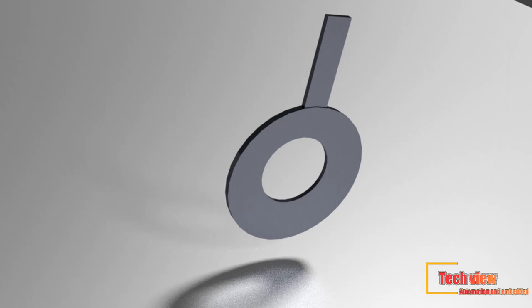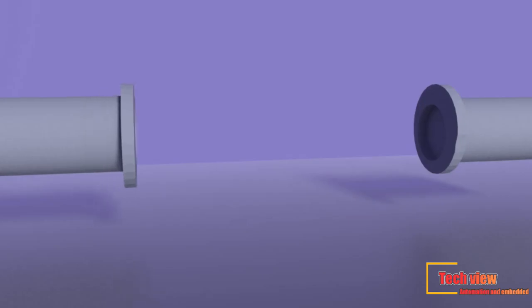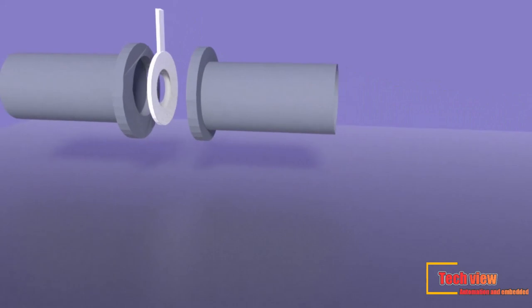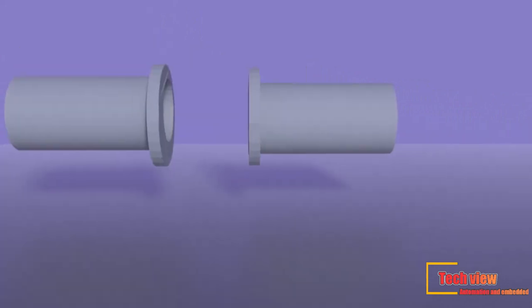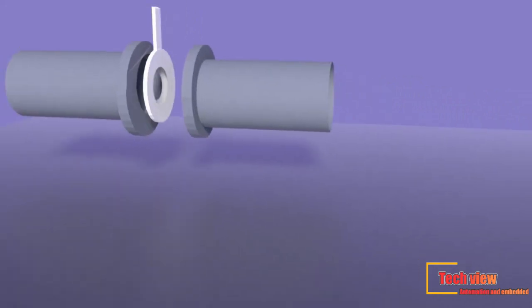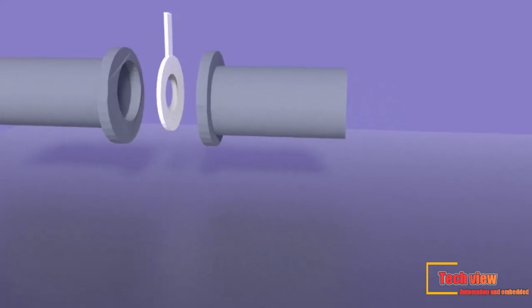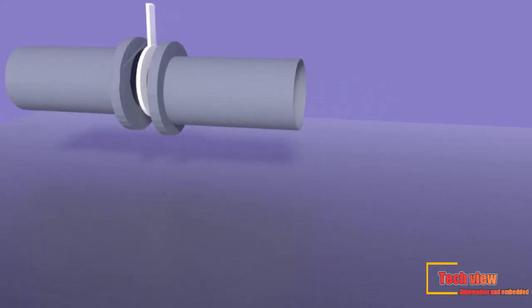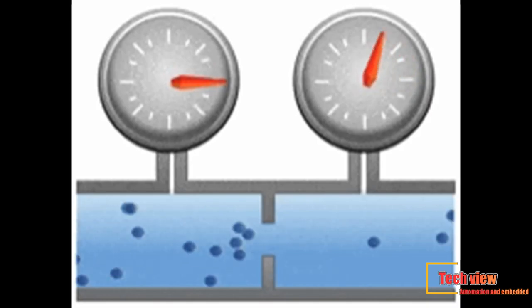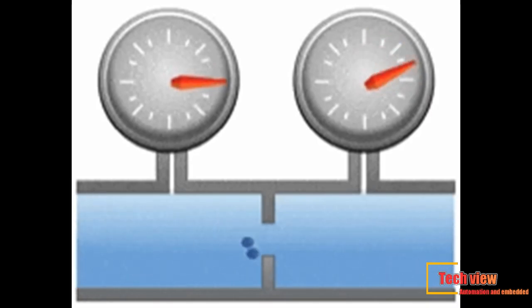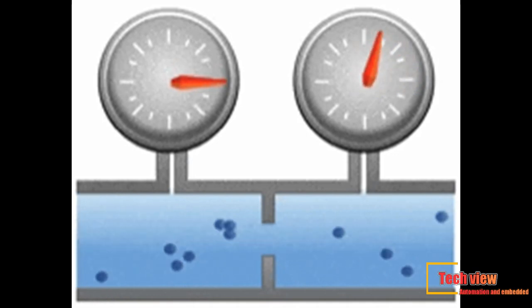The upstream side of the orifice plate usually has a sharp edge. When an orifice plate is installed in a flow line — usually clamped between a pair of flanges — the increase of fluid flow velocity through the reduced area at the orifice develops a differential pressure across the orifice. This pressure is a function of flow rate. When fluid is flowing through the pipe, the orifice plate restricts the flow and creates a differential pressure between upstream and downstream.